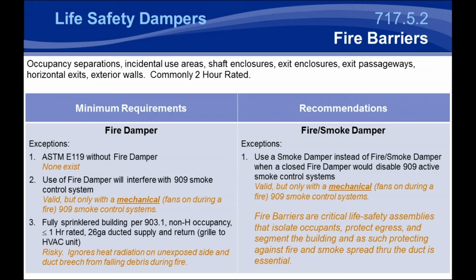protecting that opening. This third exception does not do that. And a smoke damper is not required to have that type of installation. That's typically why we recommend fire smoke dampers for these applications, as you then have a proven breakaway connection that'll withstand falling debris and make sure your penetrations are protected in the event of a fire.